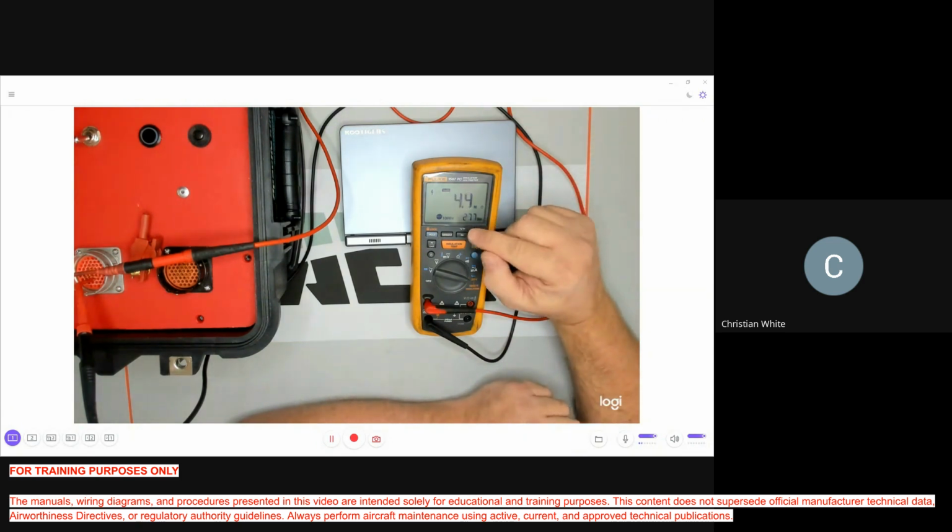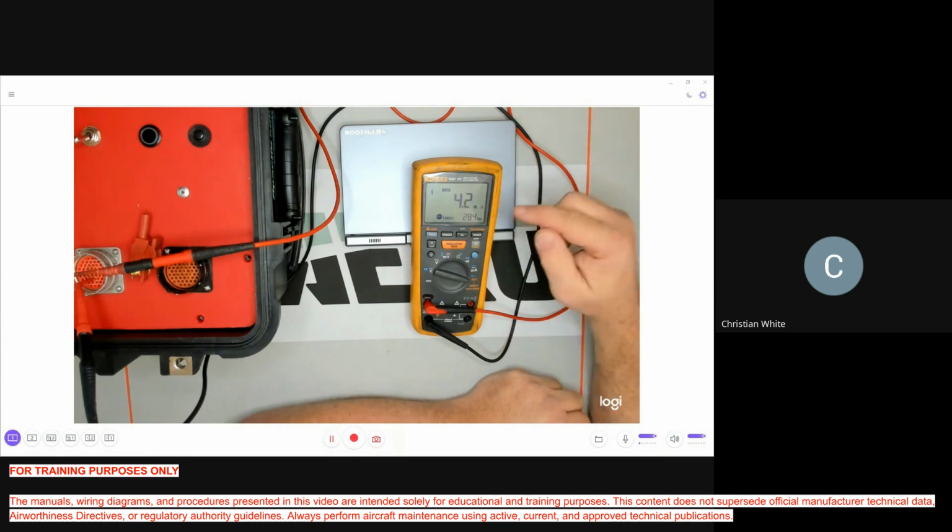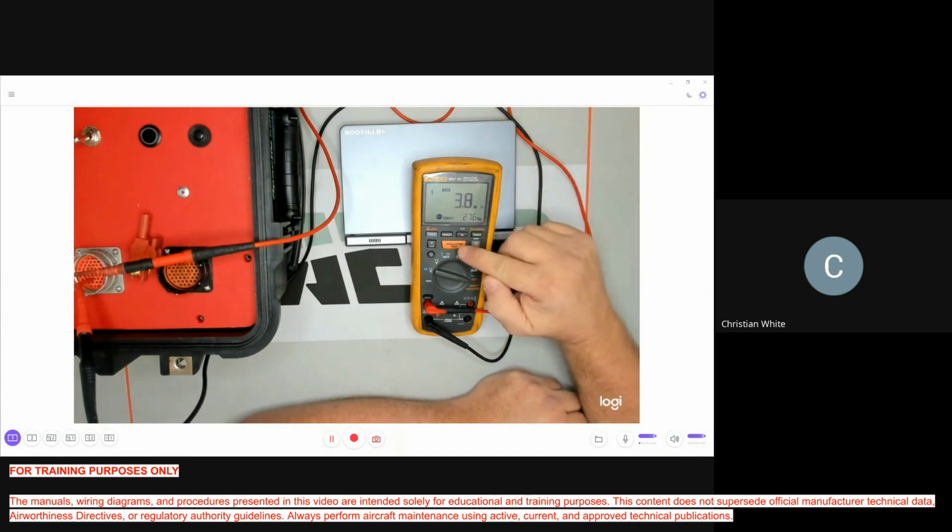You don't know. Even at 1,000, if I have a suspected wire, if I'm testing this for a known fault and I went through the wire diagram, I'm like, man, it's got to be one of these wires. And even at 1,000, I don't see anything. I may want to see if I can get my hands on that 2,500 megger, because it may not be jumping the gap, just as we saw the difference in here between the 500 and 1,000.